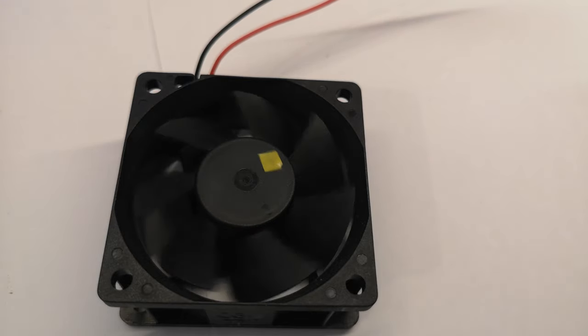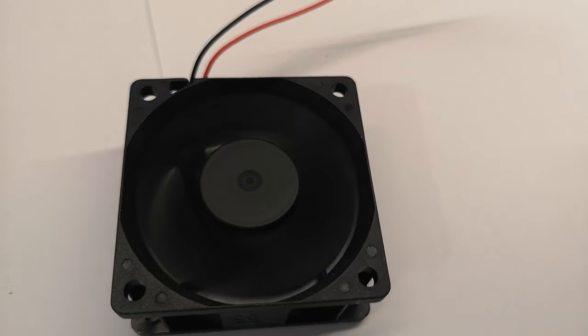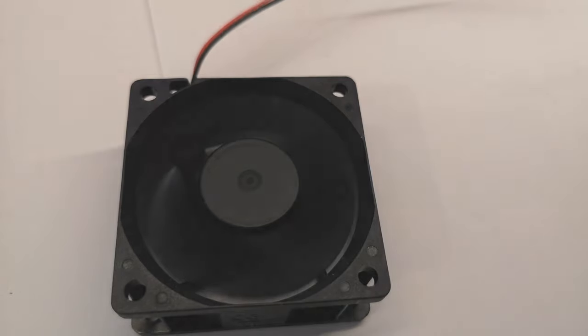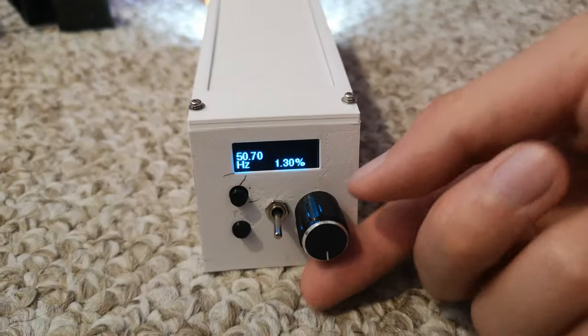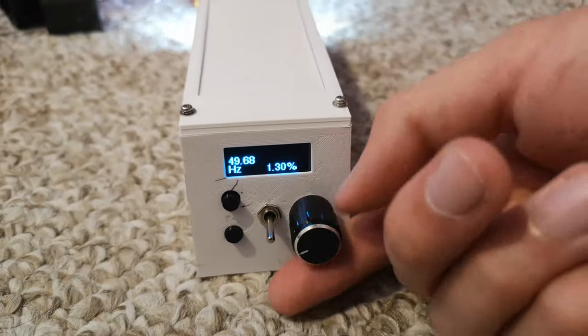In these situations, it can be beneficial for a person to manually determine the frequency using another optical device known as a stroboscope. The working principle of such a device is as follows. Essentially, if you can only see a spinning object when it is at a certain position in its rotation, it will appear to be motionless. Using this principle, the user of a stroboscope can tune its frequency to match that of a spinning object, and they will know that they have matched it when it appears to stop rotating.